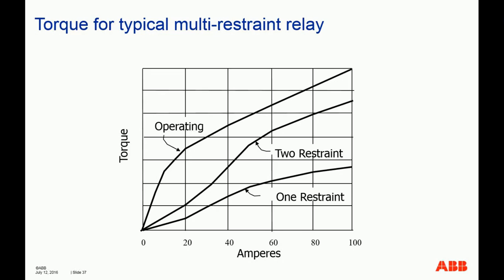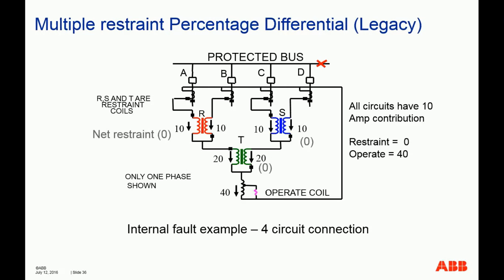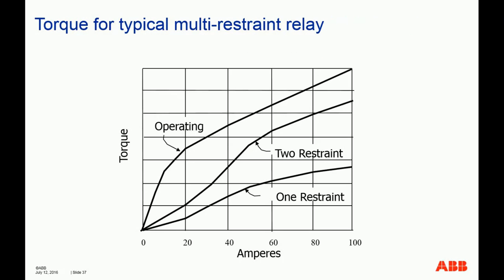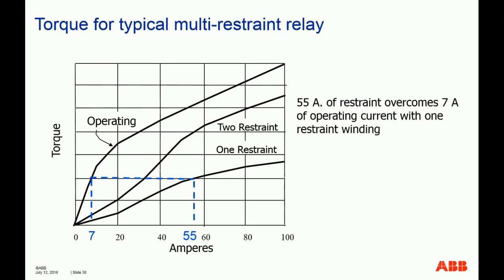In other words, if you have a restraint winding in place in your relay, it will accumulate the restraint torque, so that will end up overcoming your operating torque. That makes it more secure for external faults. As we know here, for internal faults, it's actually 0 restraint. It's designed that way so that you will operate at ease.